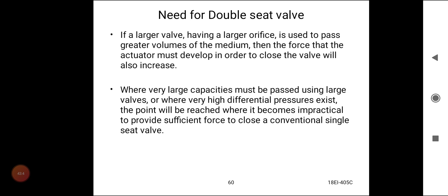Need for a double seat valve. If a larger valve having a larger orifice is used to pass greater volumes of the medium, then the force that the actuator must develop in order to close the valve will also increase. Where very large capacities must be passed using large valves, or where very high differential pressures exist, the point will be reached where it becomes impractical to provide sufficient force to close a conventional single seat valve. In such circumstances, the traditional solution to this problem is the double seat 2-port valve.